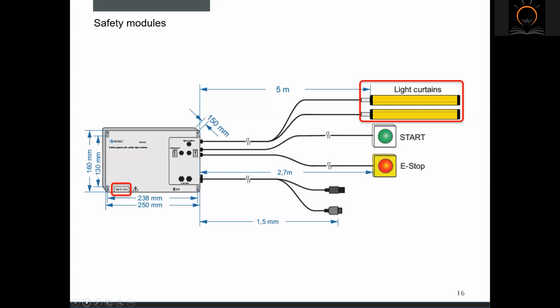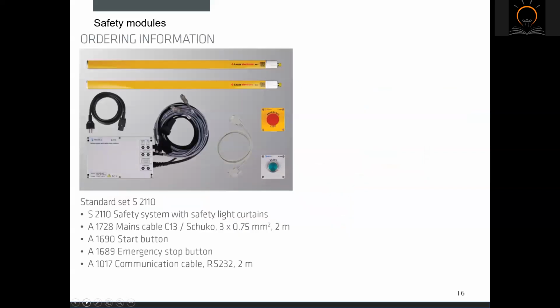Again, remote start and emergency stop, and a connection cable with connectors to be connected on the front panel of the test instrument. And the standard set of such a module is as follows. Light curtain sensors, safety module itself, mains connection cable, start and stop button, and communication cable for connecting to the test instrument.